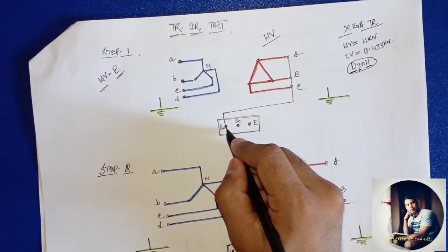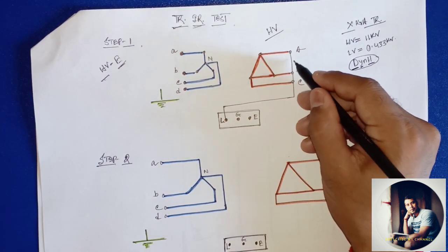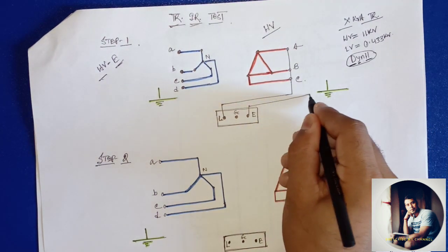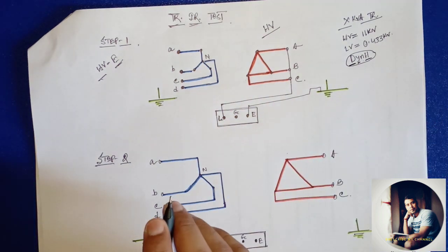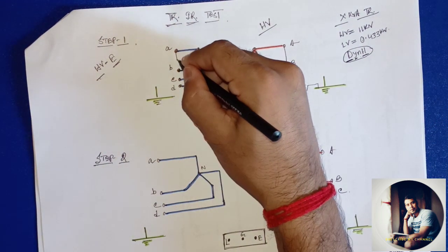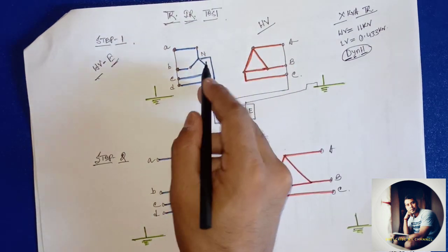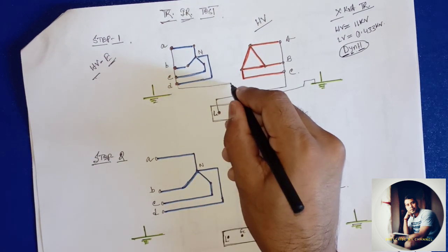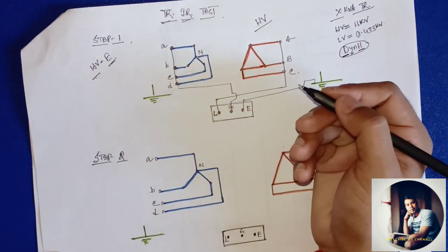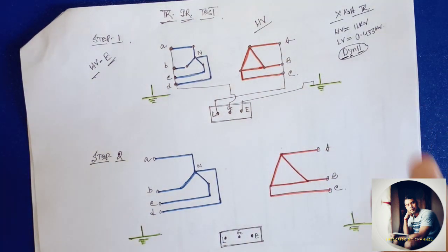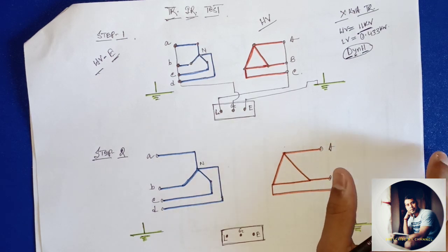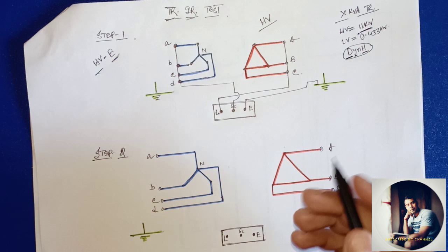The L terminal of the meter, the live or positive terminal of the meter, should get connected after shorting all three A, B, C, and the earth simply to the ground. Here it's not the end. After shorting all these four, including the neutral terminal of the star connected system, it should get connected with G, because the transformer is already a high voltage system. So in that case surface leakage current should be minimized, should be considered while taking the IR test.